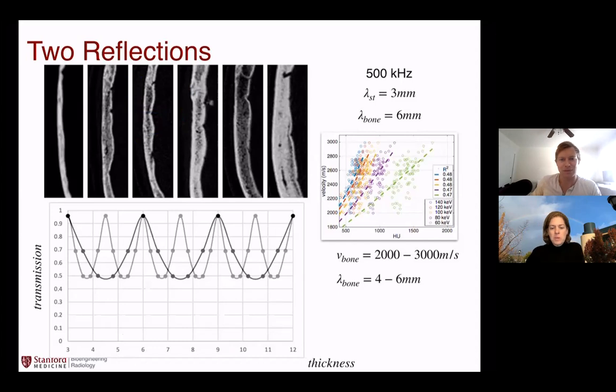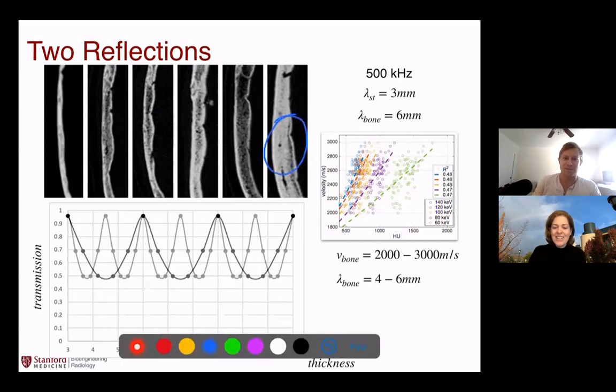And so sometimes people feel like, well, I'm going to put my transducer right there. I can get nice normal incidence. It's going to be thin and I'm going to get a lot of transmission. And it's true that I would put 99% chance you're going to have more transmission than if you put it somewhere else, but it's not always true that you're going to get really good transmission, because sometimes you get a skull that looks like this one right here or this one right here, even on the temporal window. Window, I have to put that in quotes because it's not always a good window.